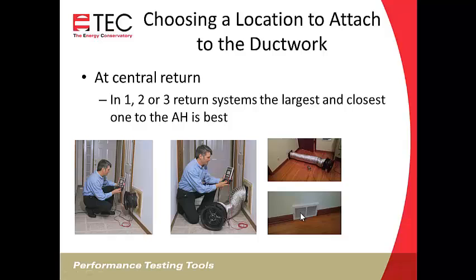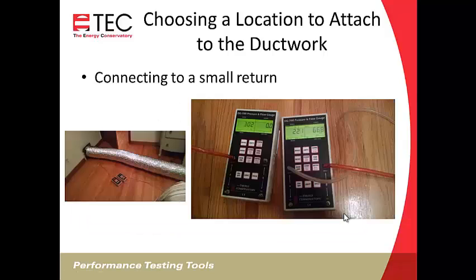If we've got a small return, which is typical in northern climates, where they'll put a return in every bedroom and a couple in the living area, if you try attaching to that, that can be problematic. So we're just showing a setup where we're attached to a small 16 by 8 return grill, and that we can see is problematic.